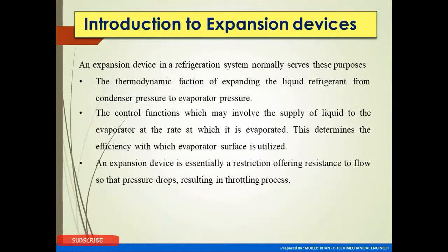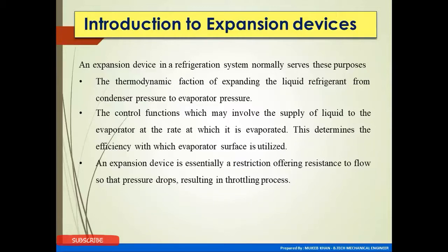An expansion device in a refrigeration system normally serves this purpose: the thermodynamic function of expanding the liquid refrigerant from condenser pressure to evaporating pressure. It also serves a control function, which involves the supply of liquid to the evaporator at the rate at which it is evaporated — this determines the efficiency with which the evaporator surface is utilized. An expansion device is essentially a restriction offering resistance to flow, so that the pressure drop results in a throttling process.